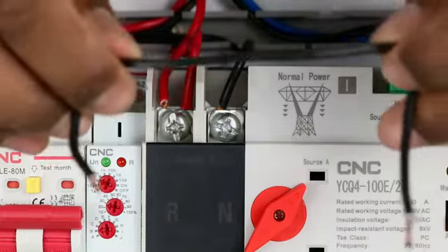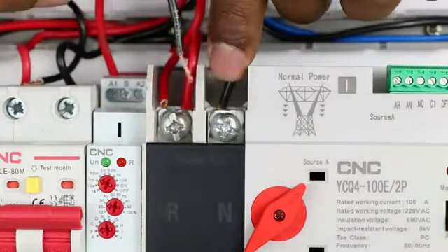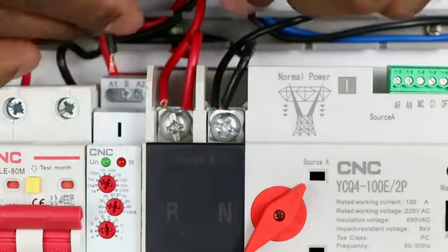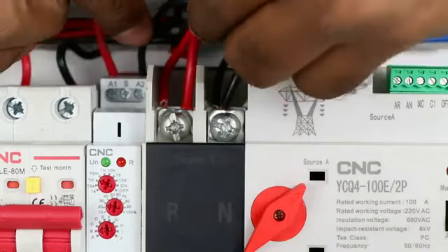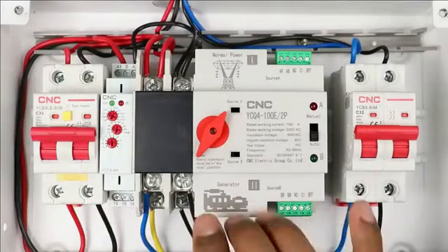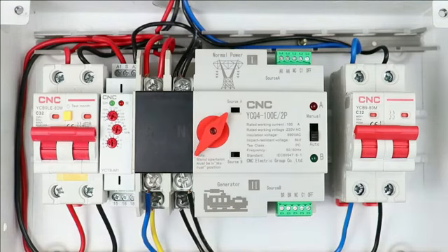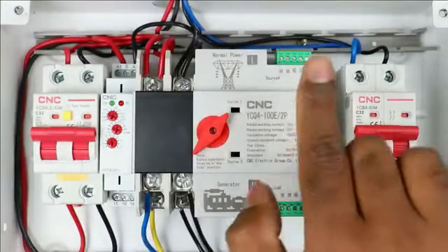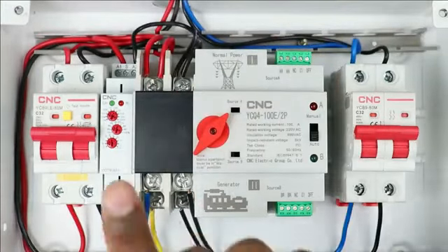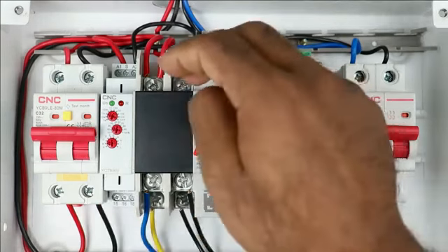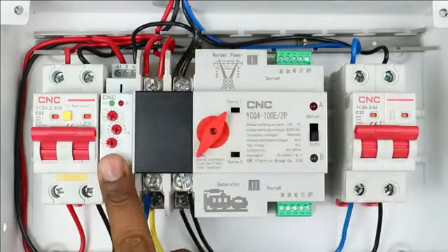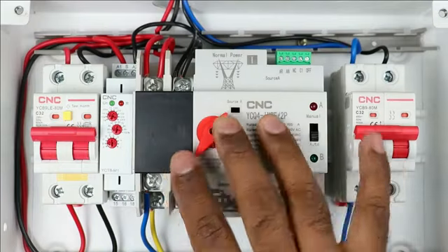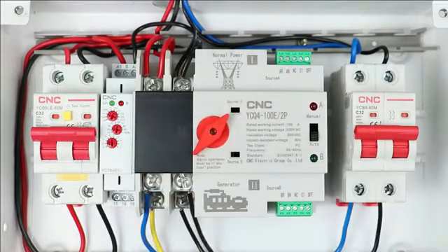I am using one more piece of wire and connecting one end of the wire with the neutral terminal of the main power supply. The other end of the wire is to be connected to the A2 terminal of the timer in this way. Why am I using a timer in this control wiring of ATS? Let's clear this concept. Before, what we used to do is from phase supply and neutral supply, we directly made connection with the control terminal. But now we introduce a timer in between because when supply comes to these terminals, this timer will operate and after the programmed time only, supply will go to the control terminal. You will perfectly understand this concept at the last when wiring will be completed.